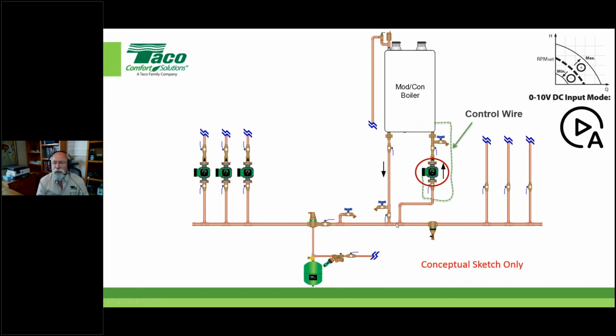I'll get into that. Anyway, understand that if you have the ability to do this, it's a good thing. The only issue is TACO makes circulators in the mid-range and light commercial sizes that have 0 to 10 technology. Most everybody, including us, uses little tiny pumps—in our world, a little 44-watt circulator—that currently doesn't have that 0 to 10 ability in an ECM offering. So my next slide will touch on why we're still talking about things, otherwise we'd just say always do this.